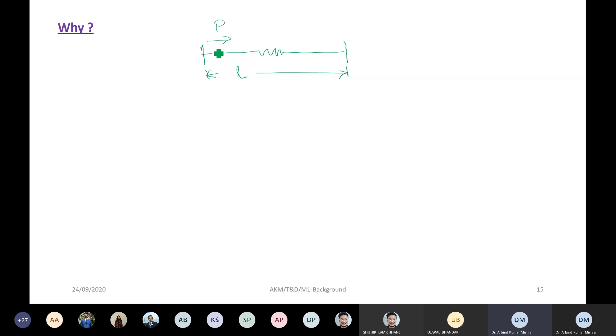The objective, again I repeat, is that P amount of electrical power has to be delivered to a distance of L meter. Then, as you know, in this line we use a conductor, and depending upon the size of the conductor and the material we use, there is a certain loss in this conductor, and that loss, P loss, is expressed as I square into R. You may say that in this diagram I have seen neither the I nor the R, so where has it come from? This I comes from this P, and this R comes, as I mentioned, from the material, the size of the conductor, and this L.